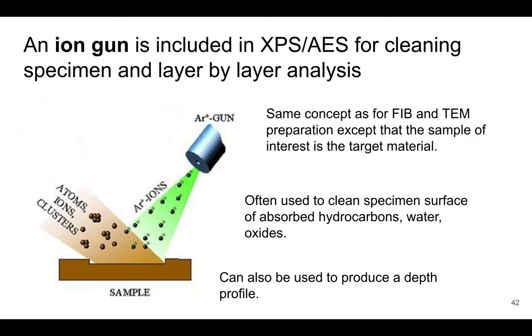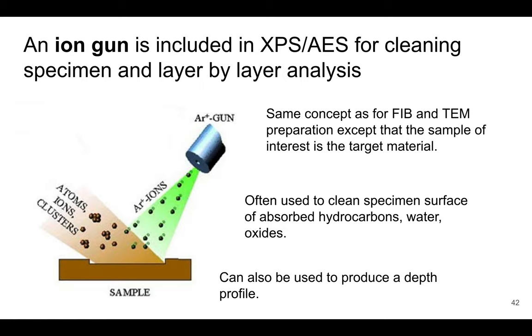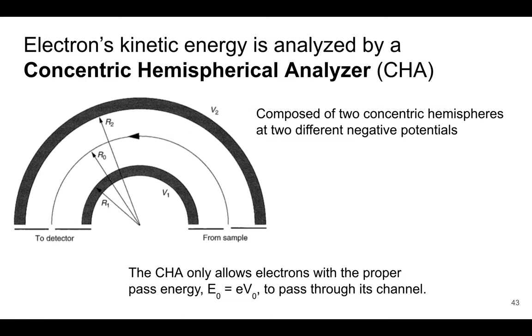The ion gun can also be used for depth profiling. After cleaning the surface and collecting an XPS or AES spectrum, if we want to look further into the material, we apply the ions again to sputter away more material and analyze the next layer. So even though XPS and AES are surface-sensitive techniques, we can probe deeper into the material by sequentially removing surface layers.